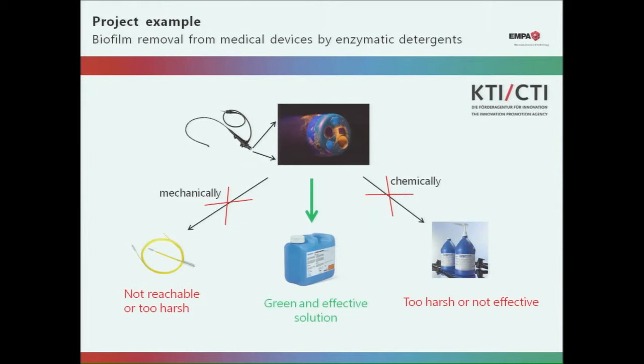They had sought to use a mechanical method to remove the biofilm, but it's simply not possible because some of the endoscope channels are very, very tiny. It's almost not possible to reach there mechanically. And also the optics on the surface are too delicate to be cleaned mechanically as well. They also tried a chemical method, but again it's too harsh because you need a very high pH, like alkaline range, or very low pH. This will harm the optic. That's why they asked us to develop a green and effective method which is friendly to the endoscope.